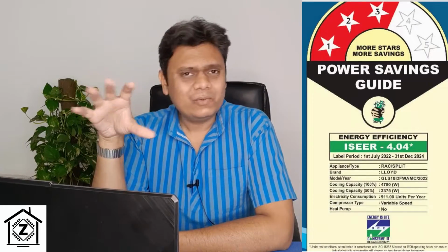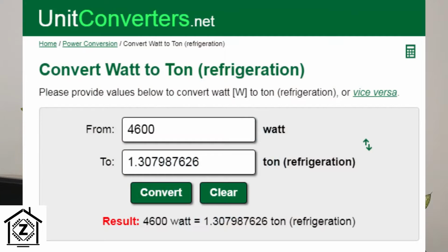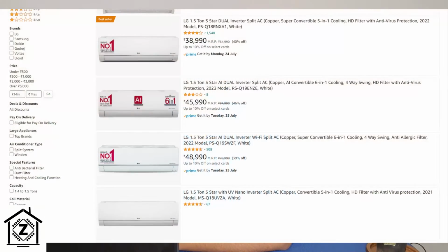I'll provide a link to a website in the description where you can enter the cooling capacity and convert it to tons. If we convert 4600 watts of cooling capacity, it comes down to just 1.3 tons. Then I get a lot of complaints that, sir, I bought this 1.5 ton AC for my room and it's not cooling properly. This happens because you haven't actually bought a 1.5 ton AC, you bought a 1.3 ton AC, my friend.